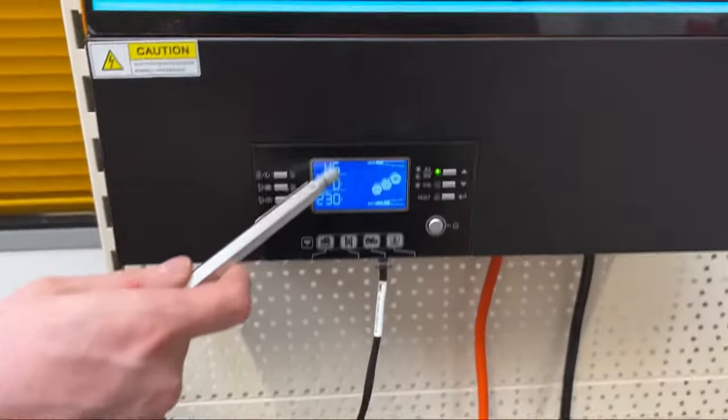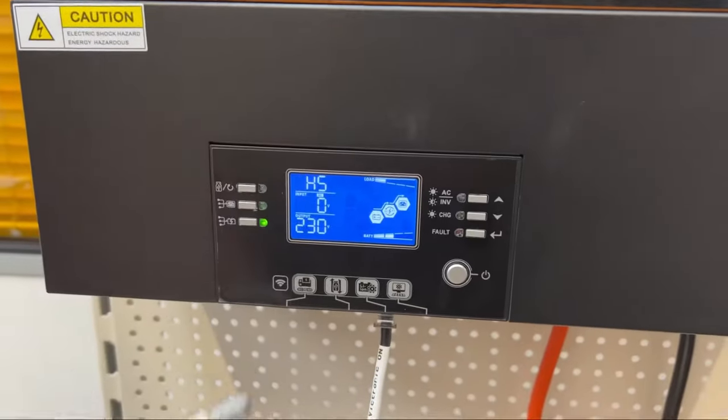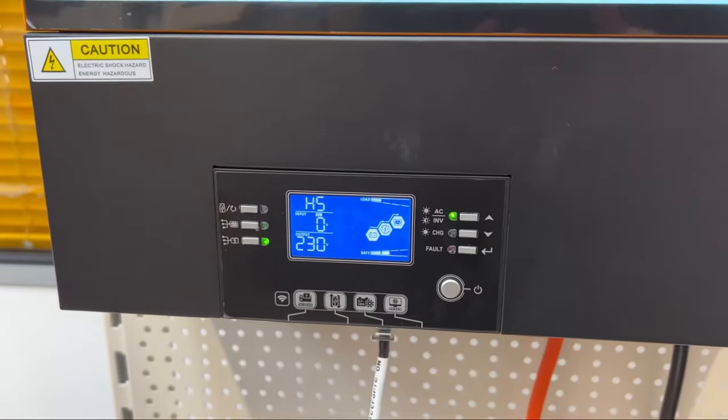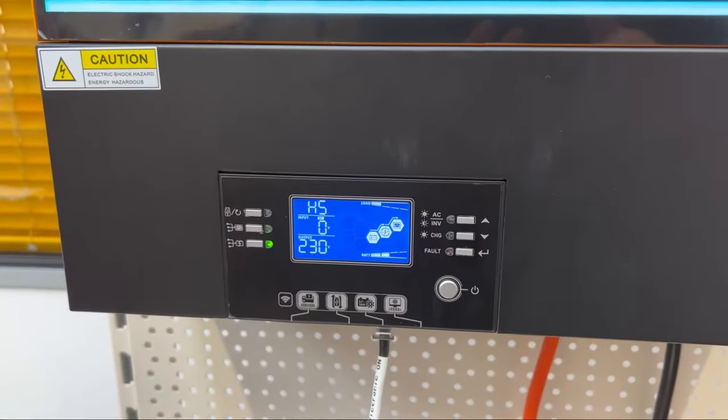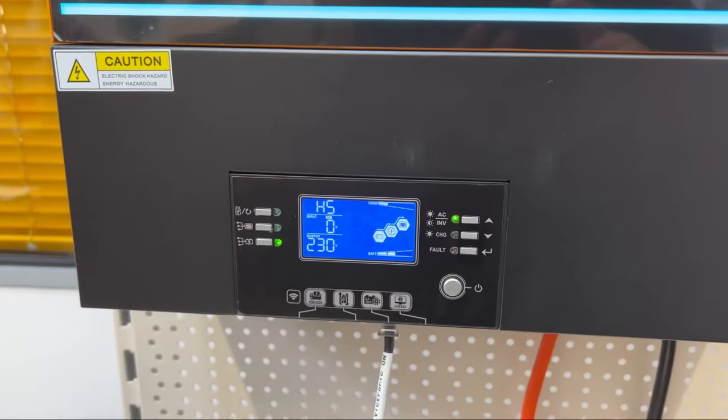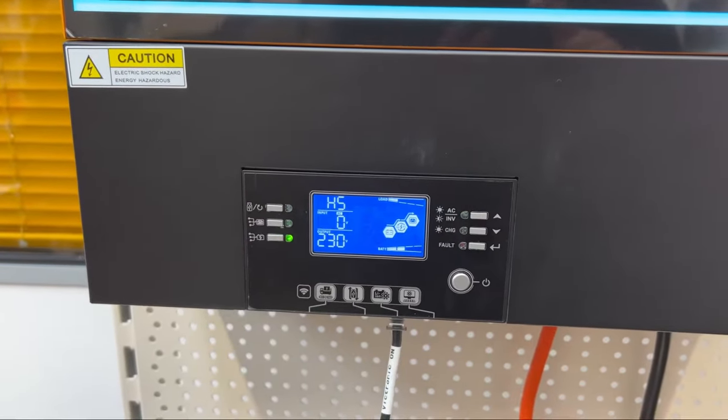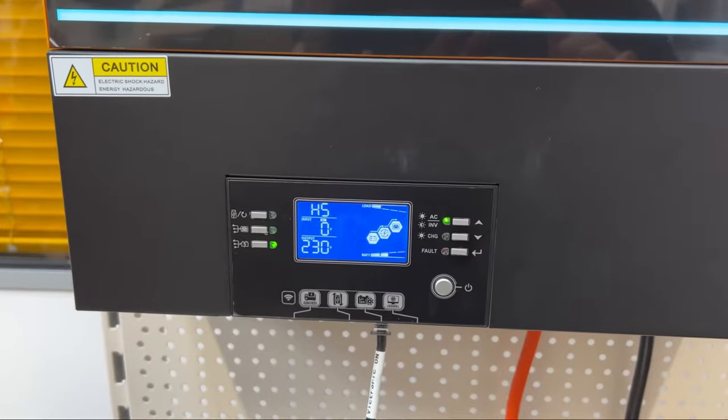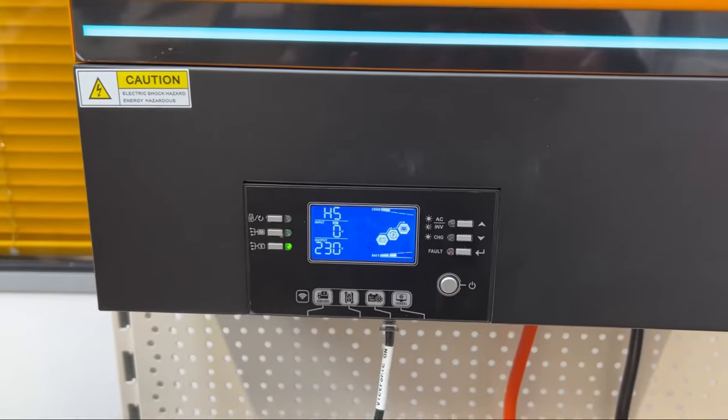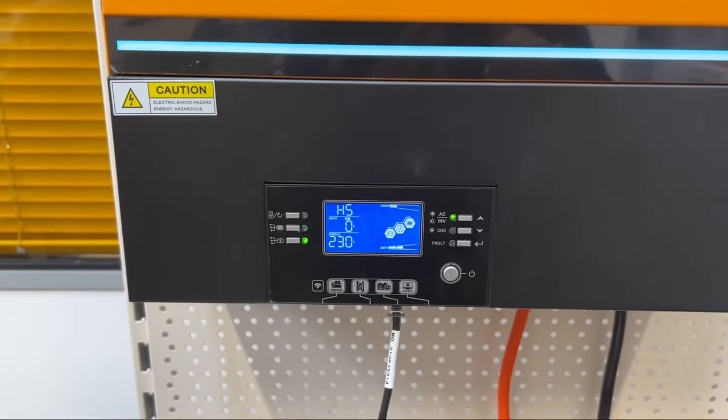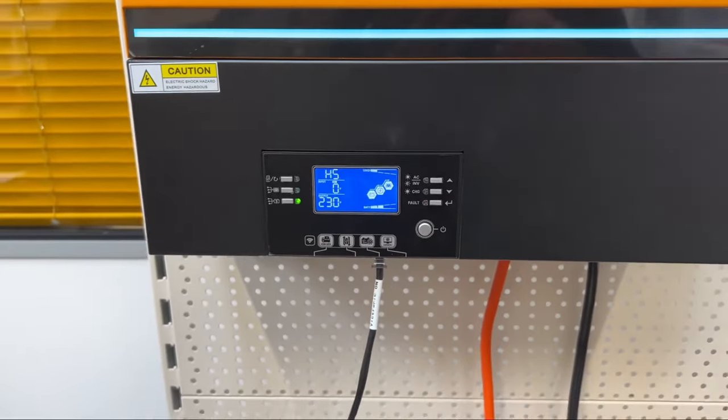If you see error 61 it means the BMS cable is wrong or the menu 5 settings are wrong. Thank you for watching this video.